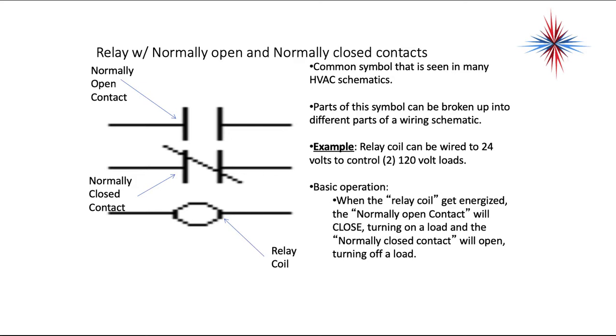We have a relay coil down here and it controls these two contacts. We have a normally open contact and we have a normally closed contact. The normal position is in its de-energized position. So the basic operation is when the relay coil gets energized or voltage is applied to it, the normally open contact will close and the normally closed contact will open.